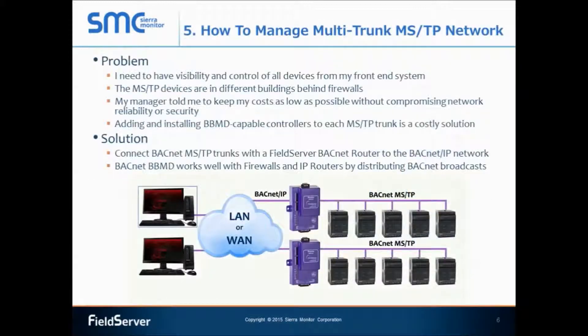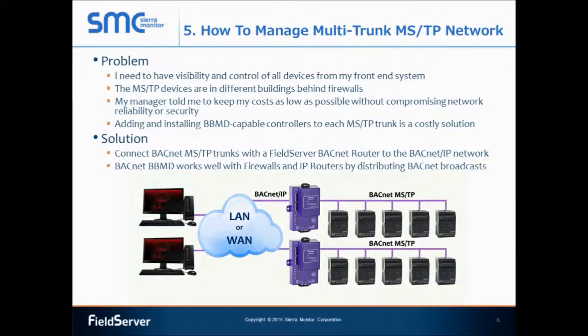Use case number five: how to manage a multi-trunk MSTP network. There are instances where BACnet MSTP devices are in different buildings behind firewalls. As a facilities manager, I would need to manage all MSTP devices as one unified network from one front-end system without compromising network security. By using the FieldServer BACnet router on each BACnet MSTP network, I can connect different clusters of BACnet MSTP devices to my BACnet IP network. The BACnet MSTP devices could be behind firewalls or IP routers — this is not a problem because the BACnet router supports BBMD, which makes the BACnet MSTP devices visible to the BACnet IP controller on the other side of firewalls or IP routers. It also allows for connection between different subnets.